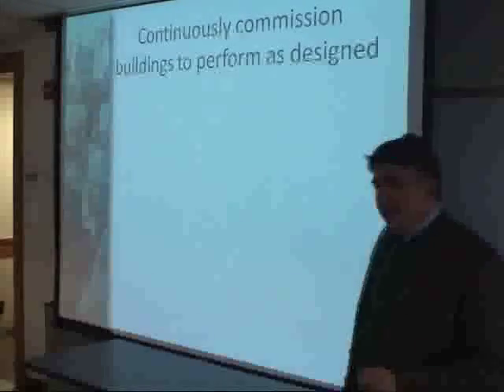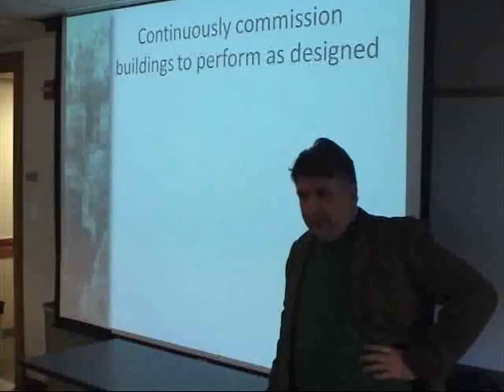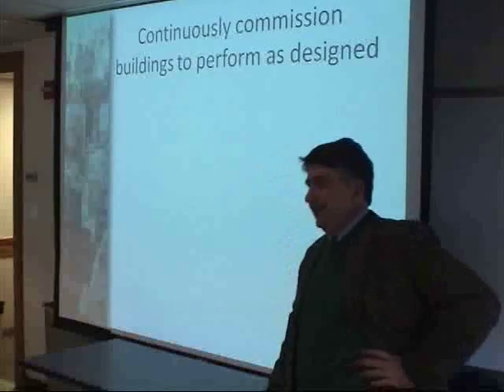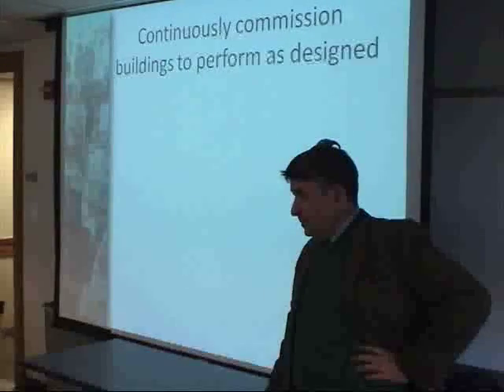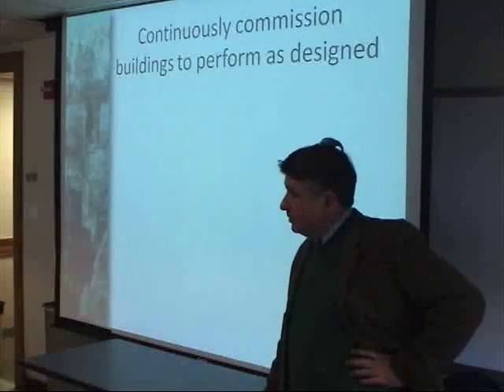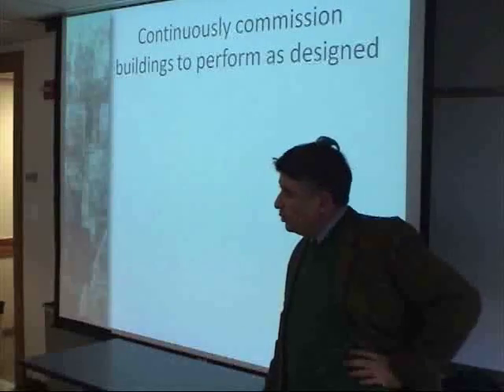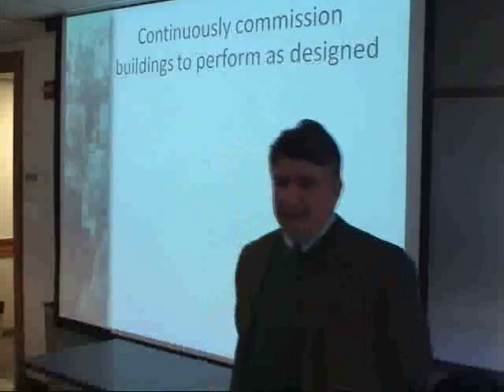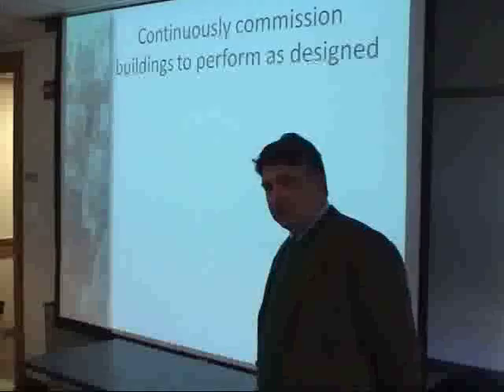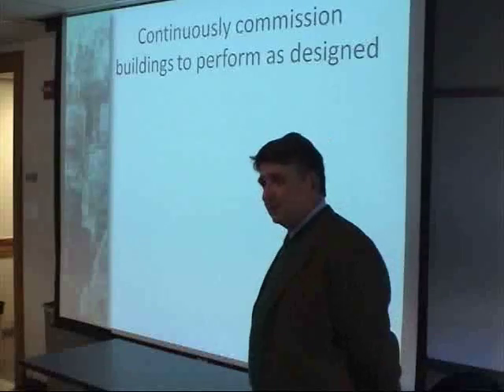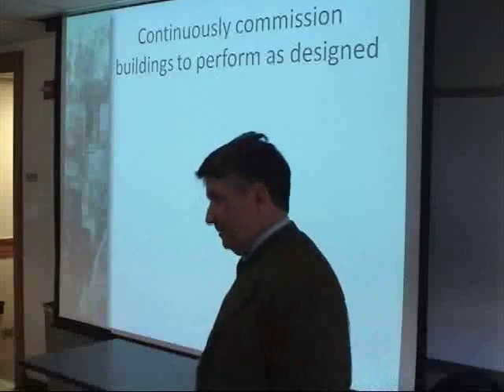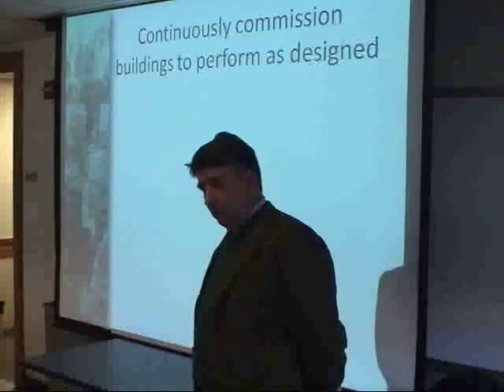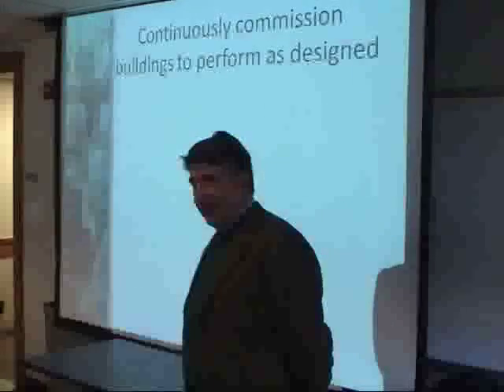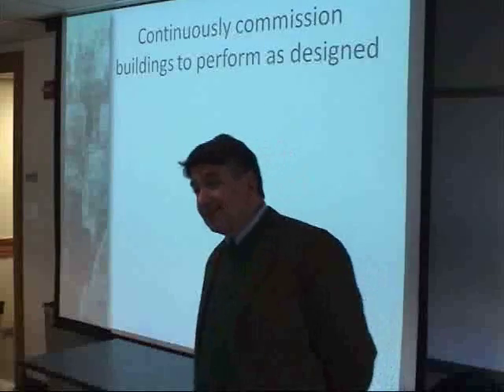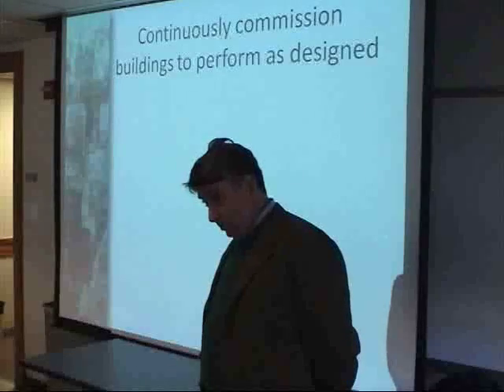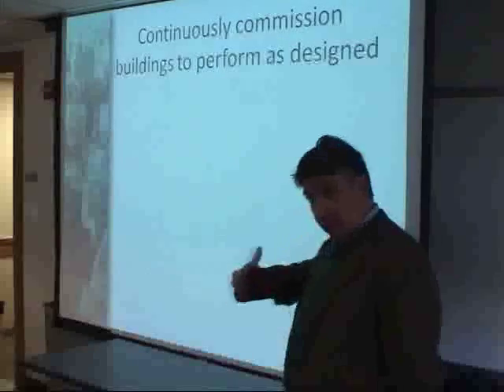Now, if I have live feeds and can somehow read information from the control system in a standards-based way, then not only can I commission the building day one, but we should be able to look at the performance of each system every day and tell you, is it still in commissioned state? Not just was it hot or cold, but is it performing as designed? That's a big difference from the normal model. Quite frankly, that's now a hot area of discussion within the standards world, and there's clearly a big win there.